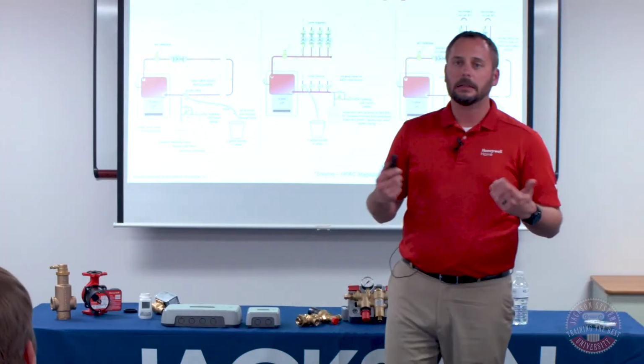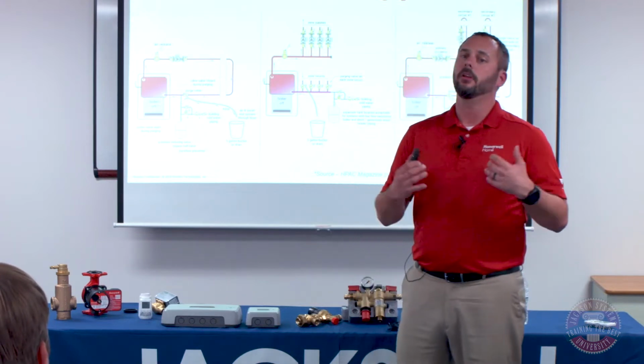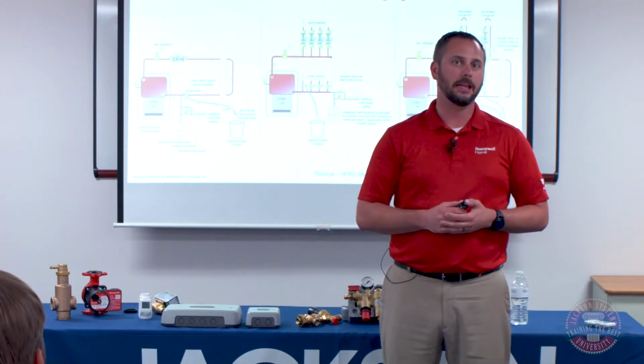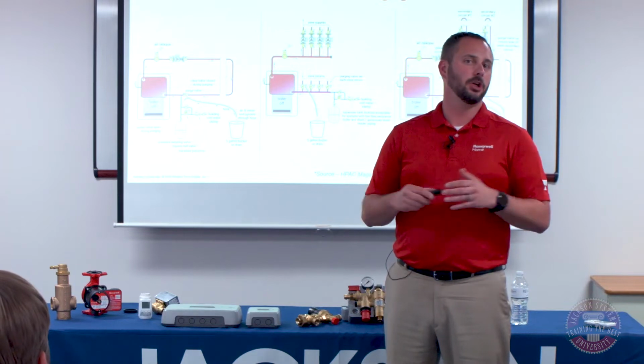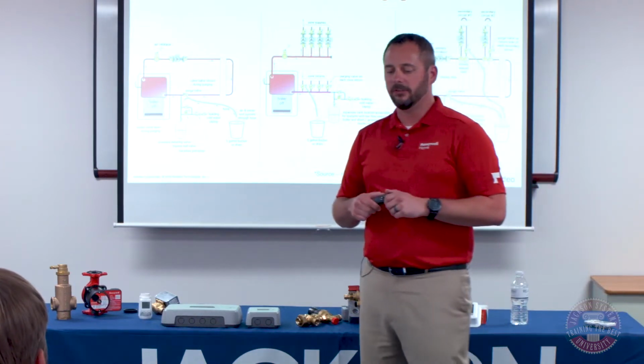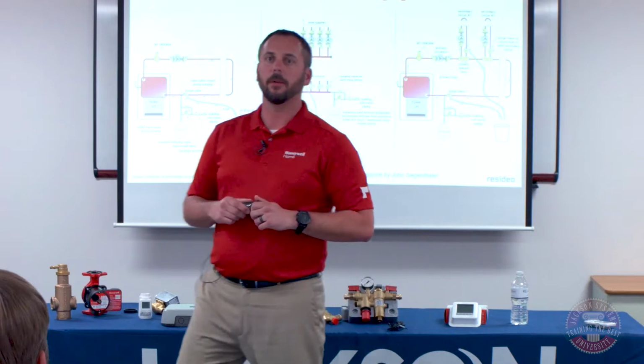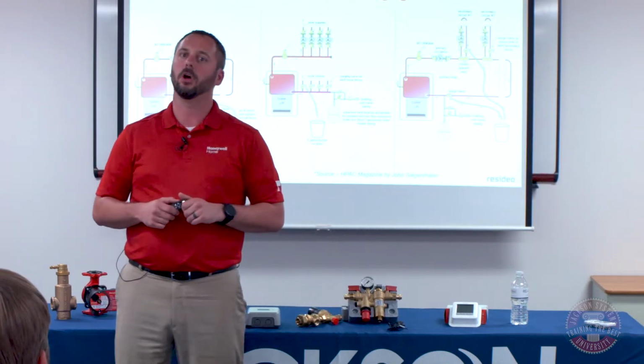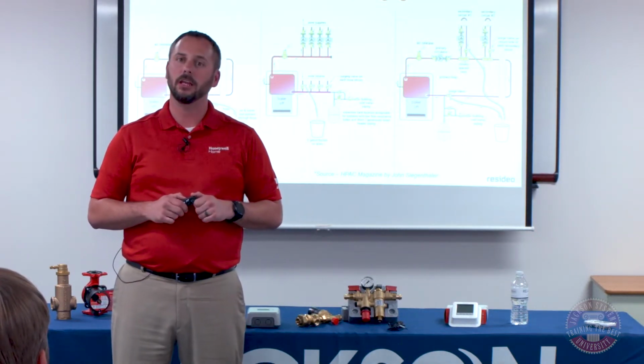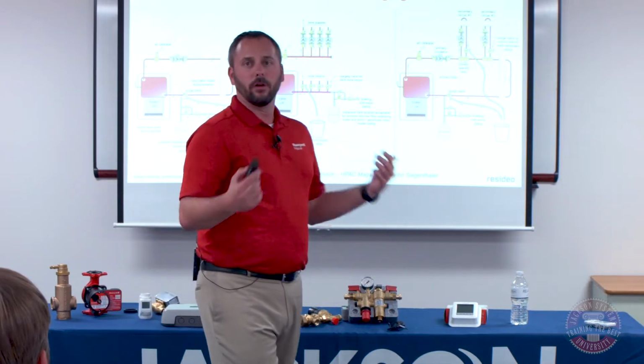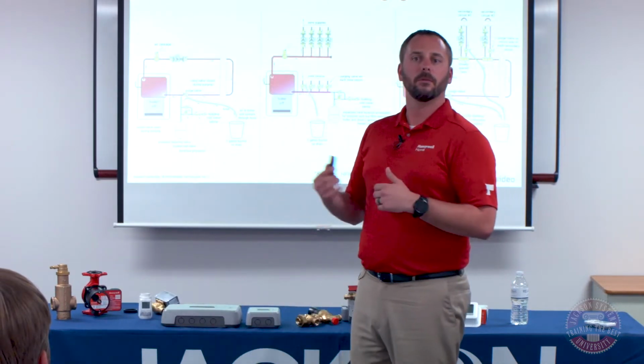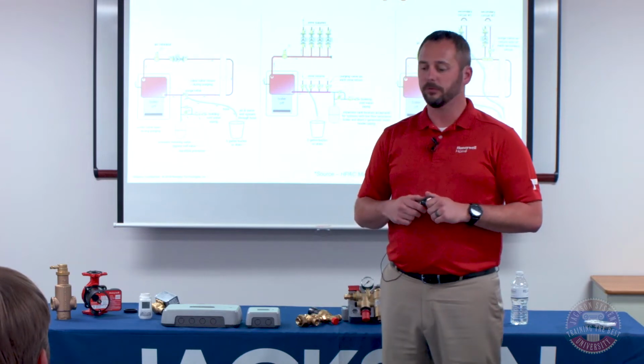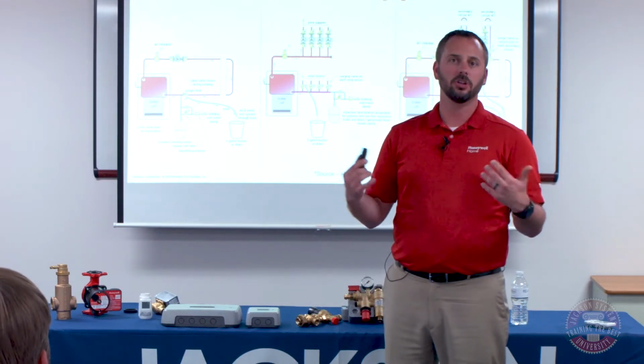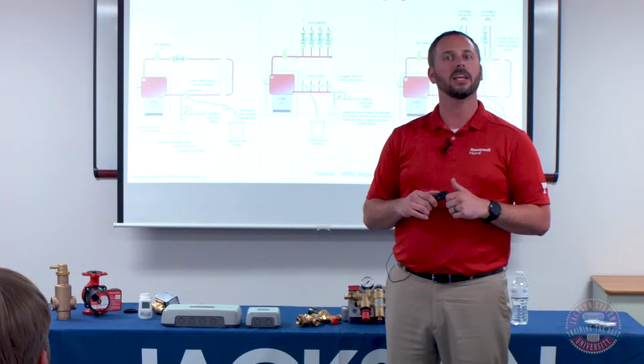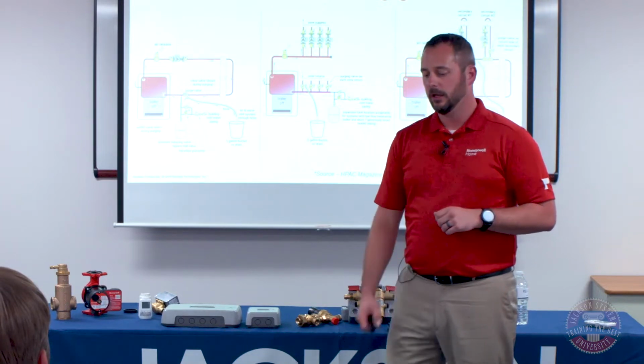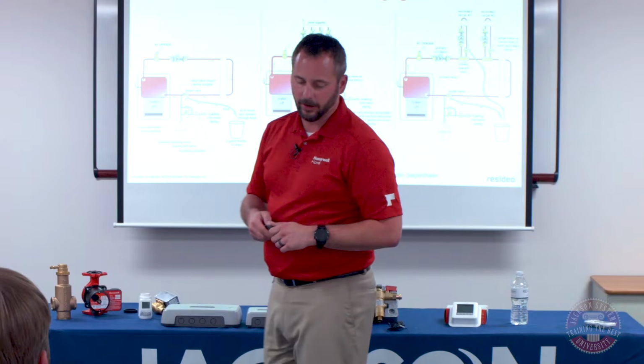And then last but not least, I've just got another diagram here. There's so many different ways to plumb a hydronic heating system. I'm just showing a couple different diagrams here. In this instance, you've got a couple different loops coming off of there, different characteristics on the flow rates. So we've got closely spaced tees, so you can drive one flow rate around the boiler and multiple different flow rates in the secondary loops. So in this example, again, just showing you how to purge some of those out so you can get proper movement through there. Get everything balanced to the same pressure and get all the air out of there.